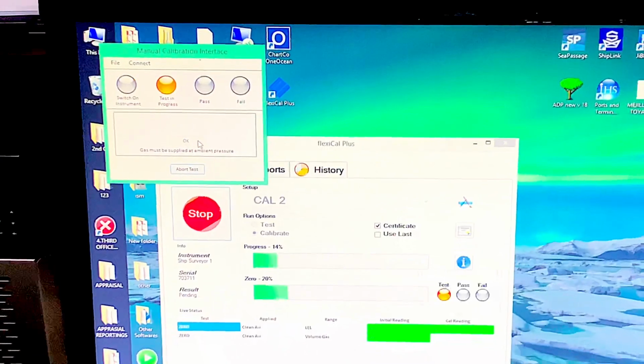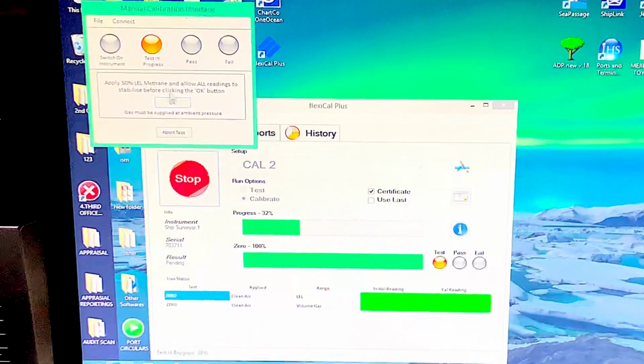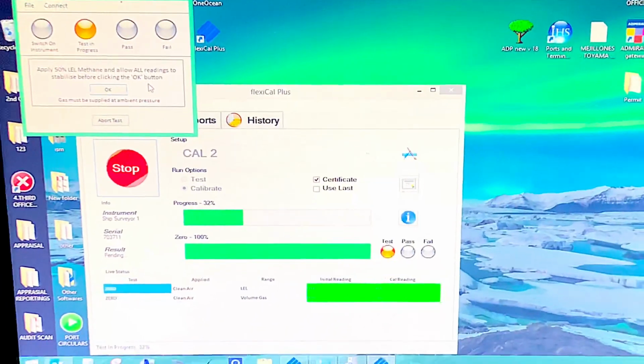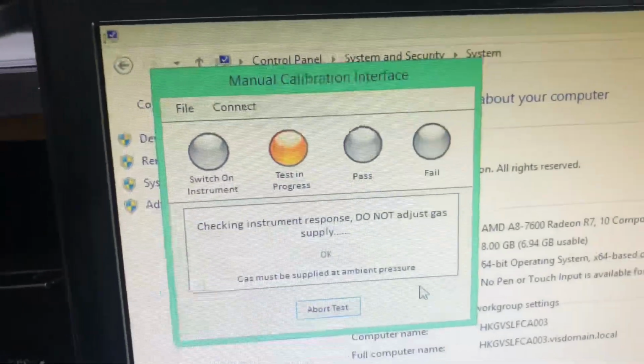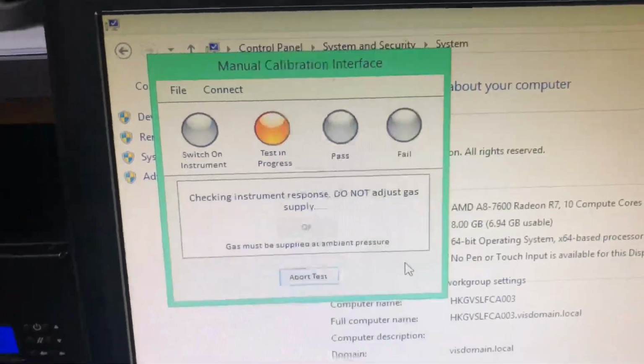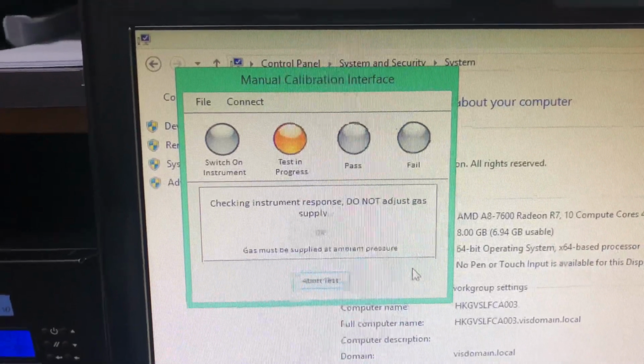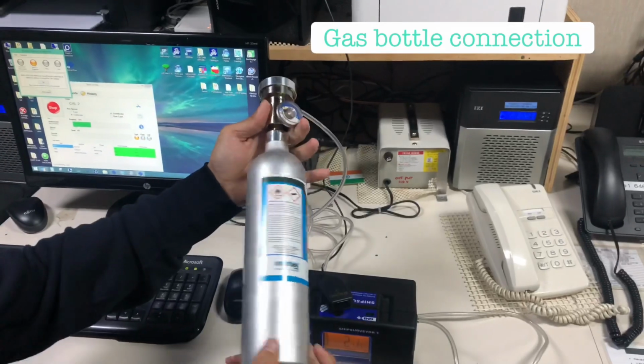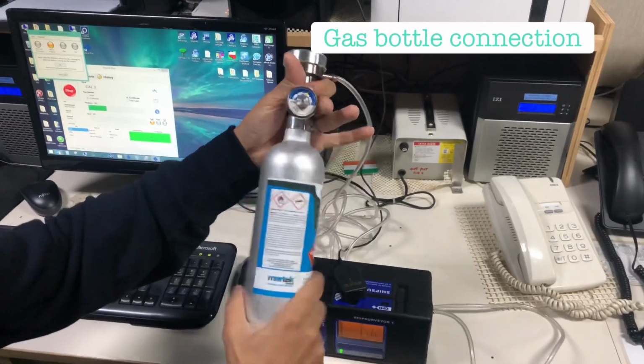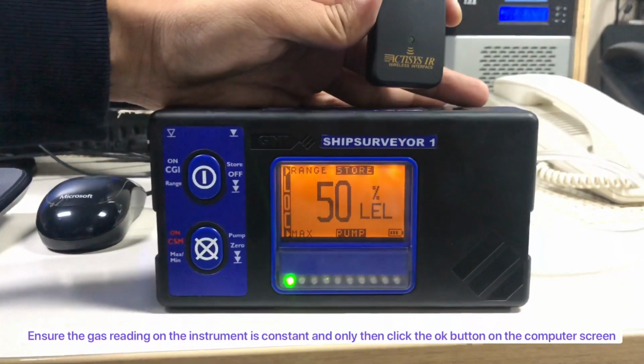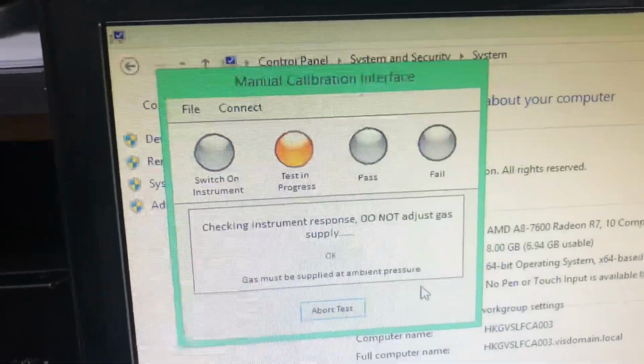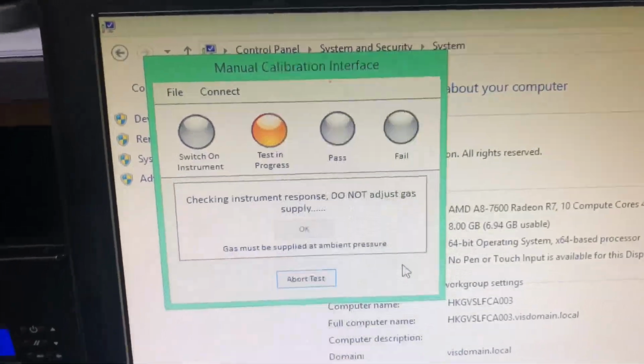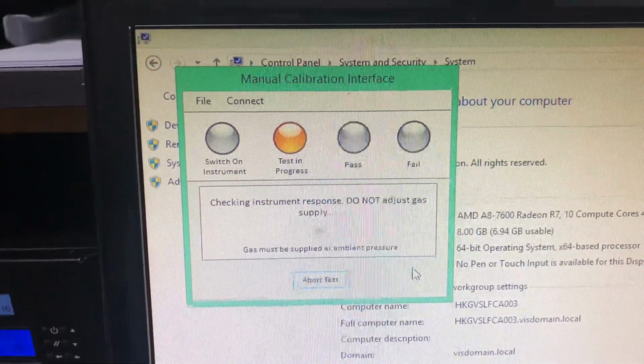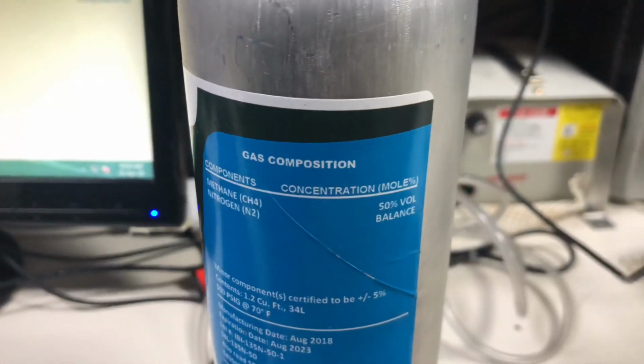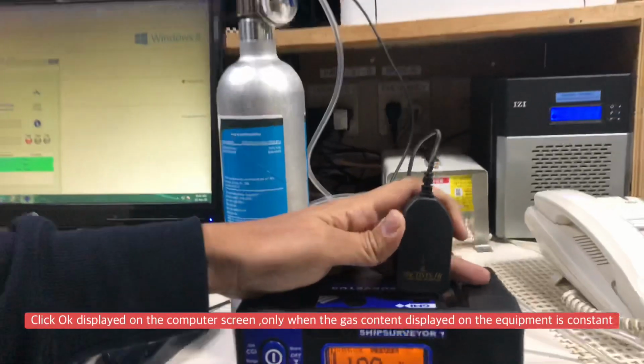So the instrument is presently being calibrated with fresh air. Once the instrument has been calibrated with fresh air, the next step is to calibrate with 50% LEL methane. Once the gas reading is constant, click on the OK button and wait for the further instructions displayed on the screen. Connect the gas calibration bottle with 50% volume methane to the equipment.